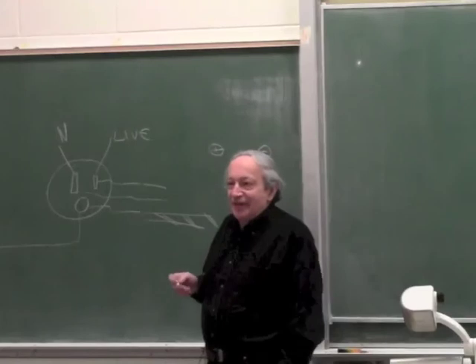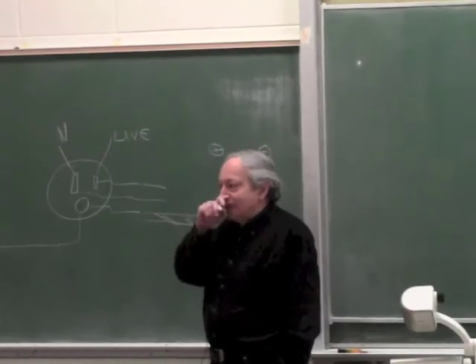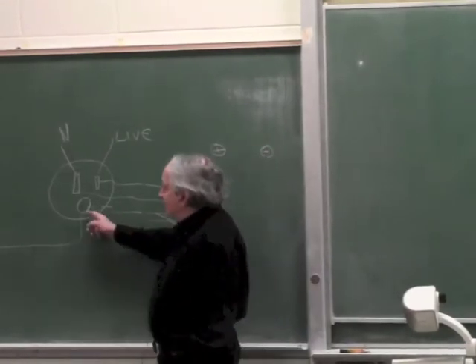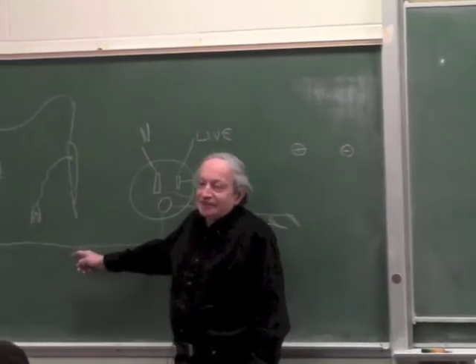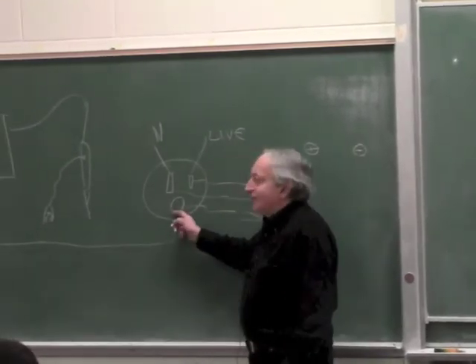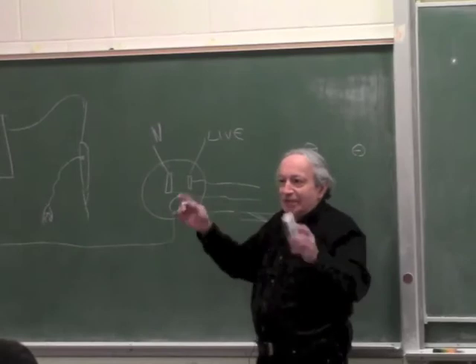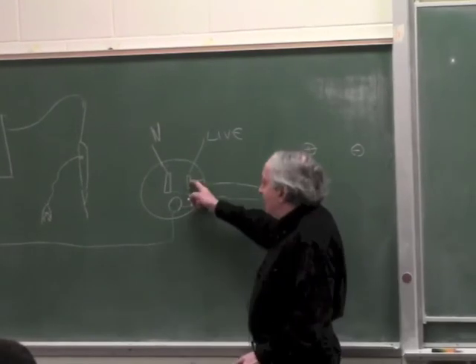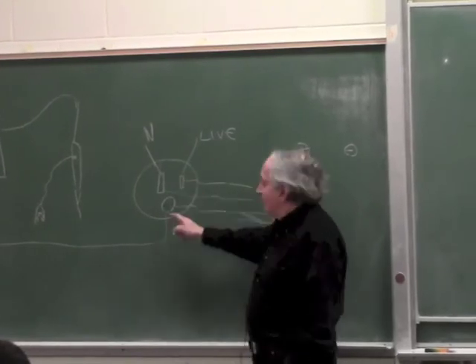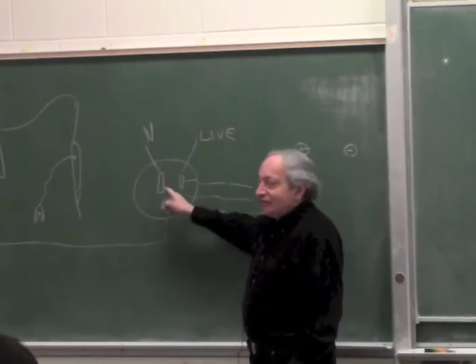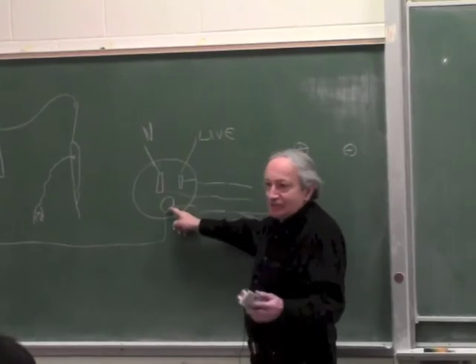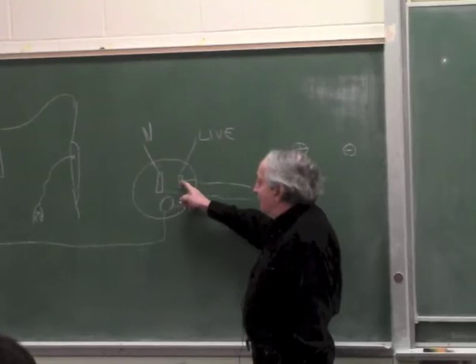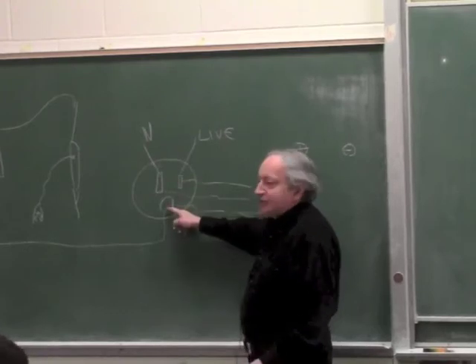So again, ground loop is created by the fact, and I'm just reminding you from Tuesday, that in theory this ground should carry no currents. In theory this ground is only for safety, so if the metal case of the body touches the live wire, it will blow the breaker, because the ground is like the neutral. This is connected to the case of the equipment, so if a wire chafes the insulation and touches it, it will blow the breaker.